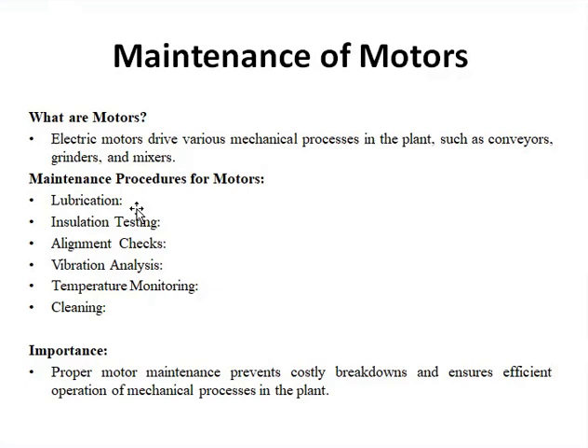So bearings in the motors need lubrication to function smoothly. For example, lack of lubrication in a conveyor motor would cause overheating and eventually failure. That is the main thing. If the motor is facing some complication in running, it will draw a lot of current and it overheats. So you have to make sure it is running smoothly and it is lubricated.